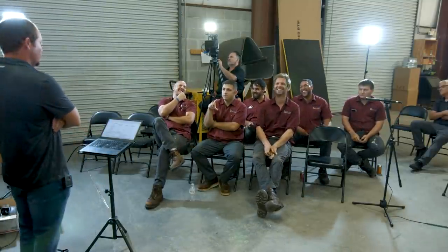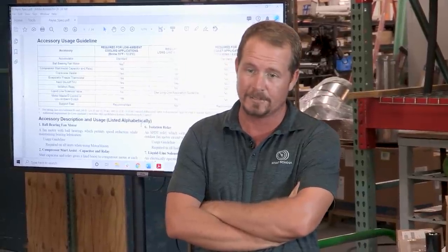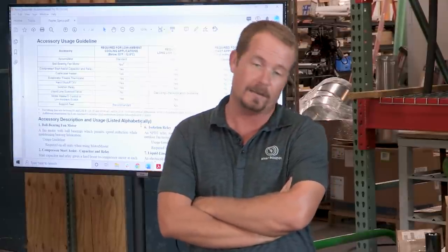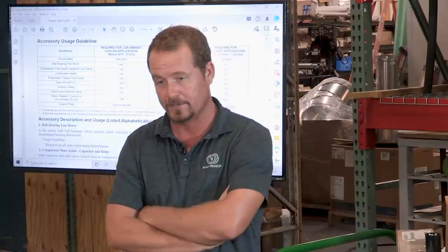So if we use the factory relay with a universal hard start, it's all about the capacitance. If the capacitance matches the factory capacitance, you don't need to use a factory kit. Yeah. You could get a potential relay of the right size and a start capacitor of the right size, put them together, and you've got yourself a hard start kit. That's what a hard start kit is.